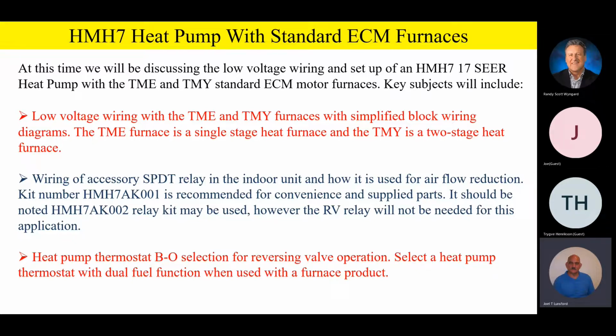Now the wiring of that accessory single pole double throw kit in the outdoor unit is going to be used again for airflow reduction. So I won't read all the way through that again. Just remember the 001 is for convenience and supplied parts, for single stage operation and two-stage operation in this example. And then the 002 kit is going to be for the variable speed product.